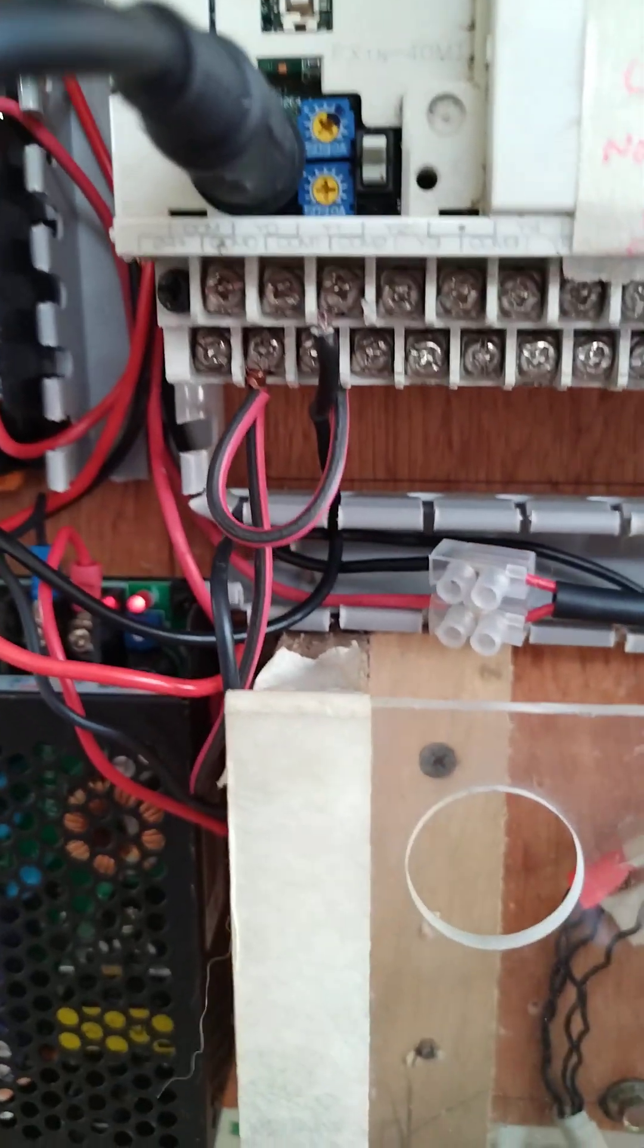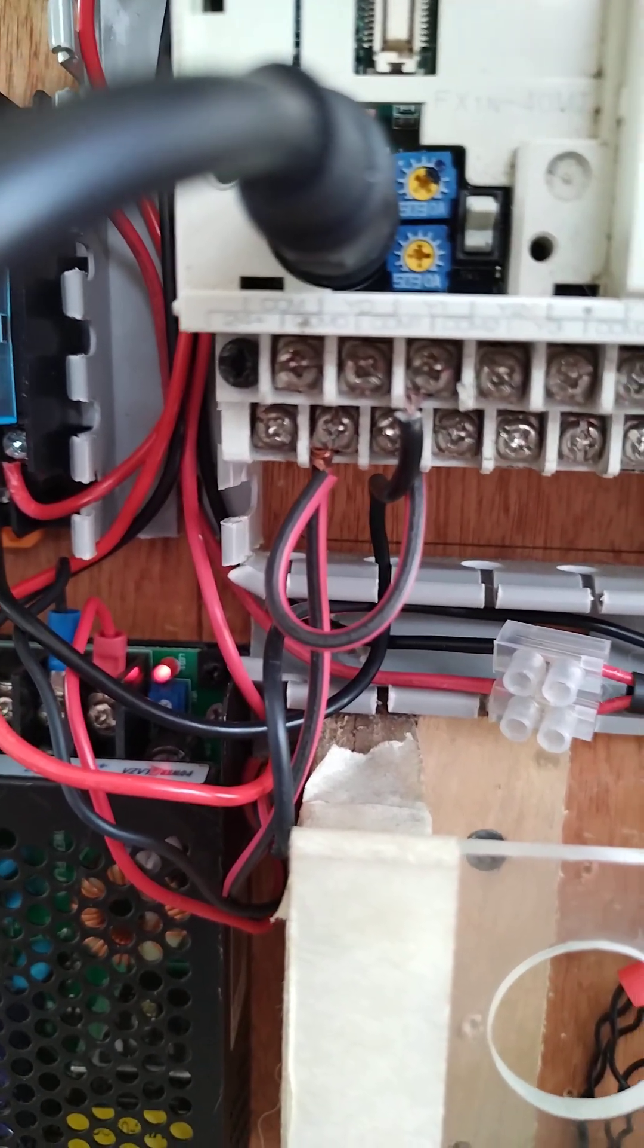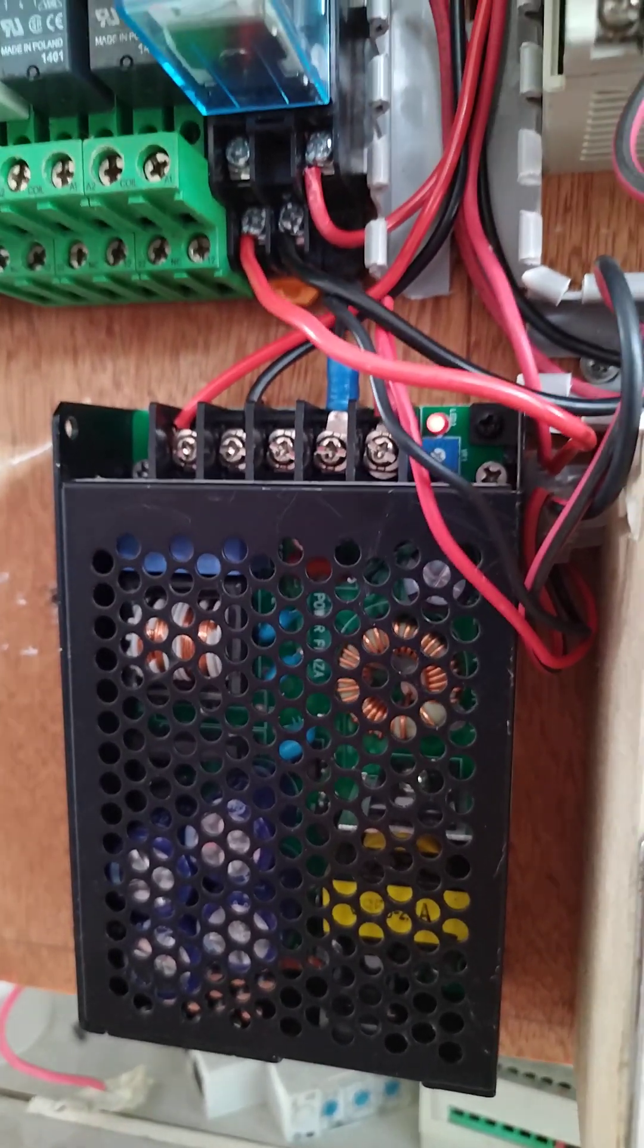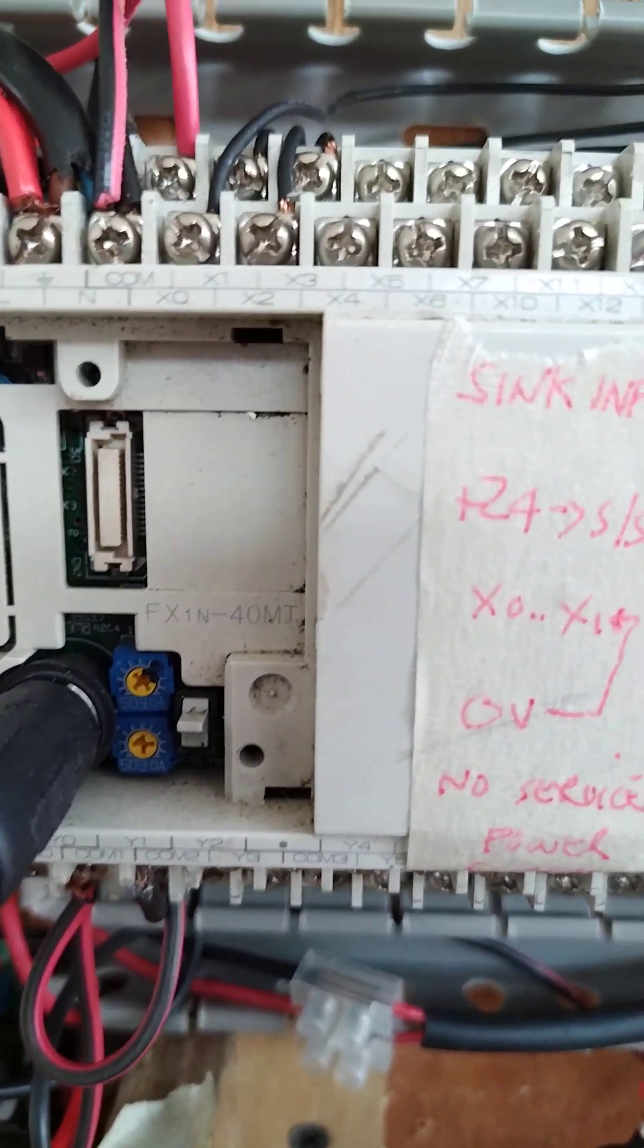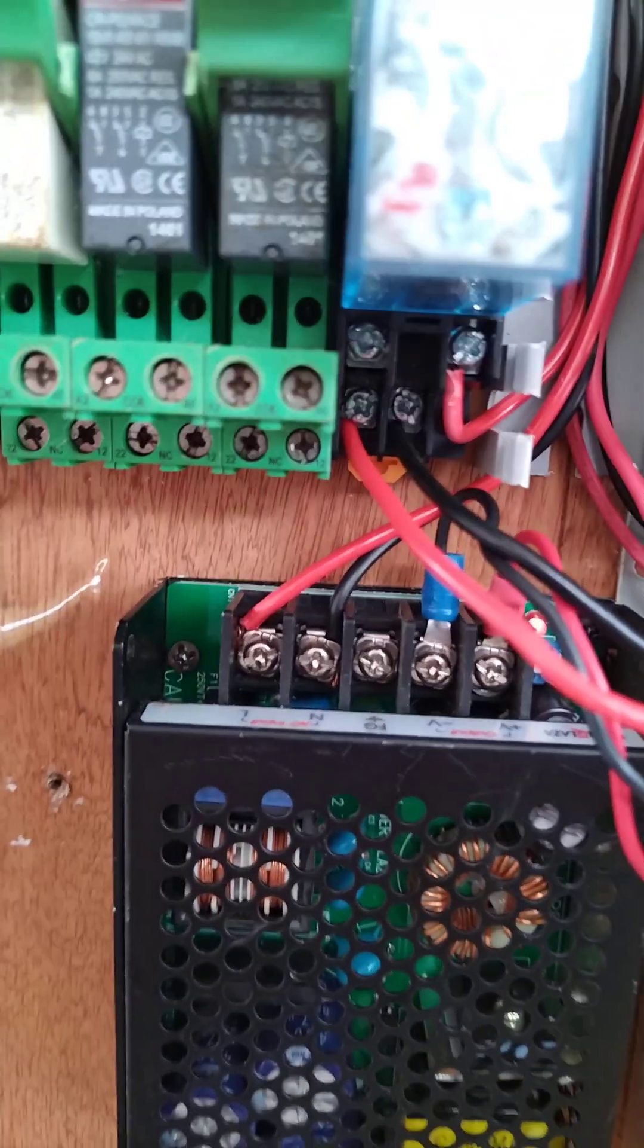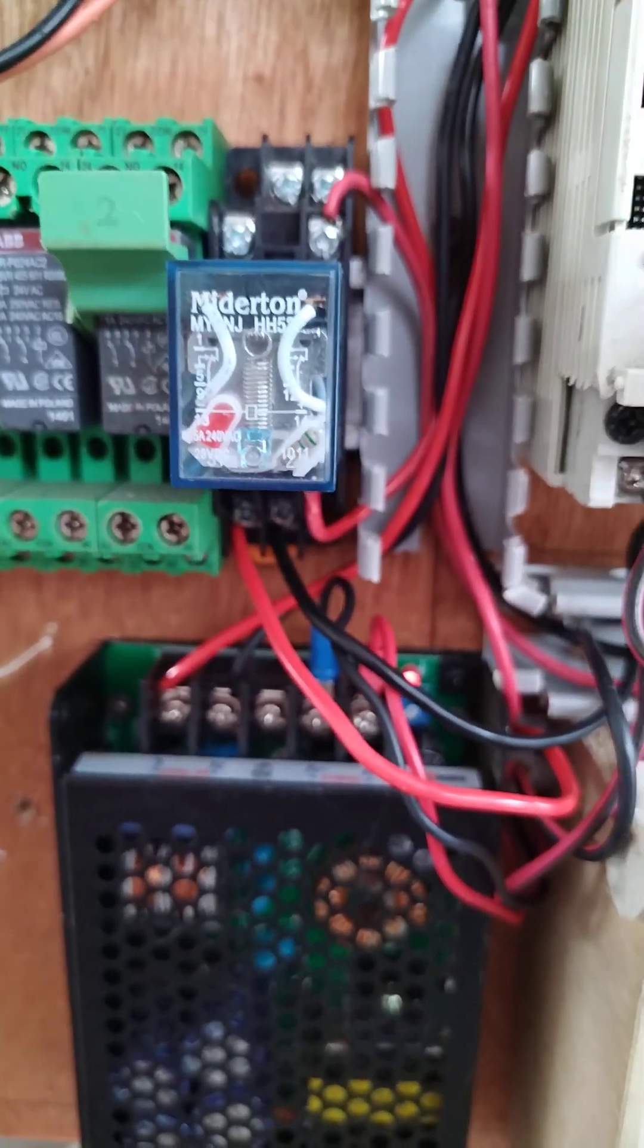Now the problem here, this PLC, the service power supply is not working. That's why I need to use an external power supply, 24 volts DC, so that it will be fed to my negative that will trigger my inputs. Then the positive 24 volts that I will be needing to power up this 24 volts DC relay. I'm using the normally open contact and the common. I'm feeding 220 to this 220 motor, small motor.